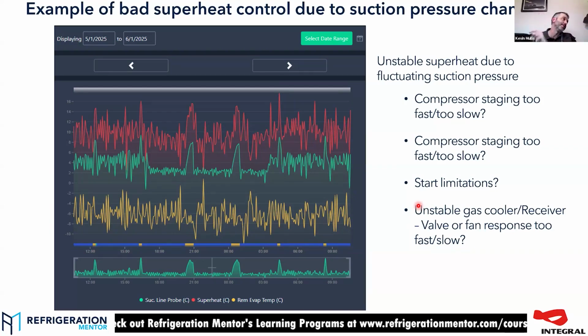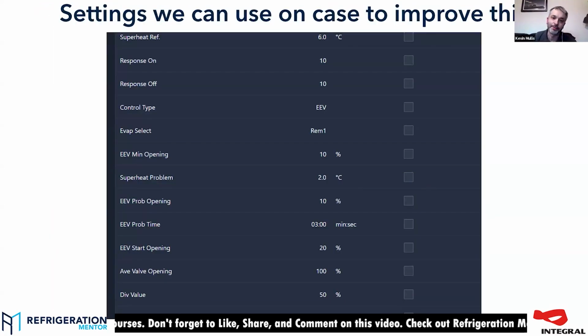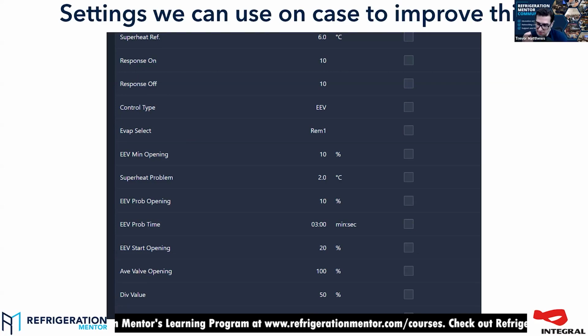Obviously, the other point about keeping the high pressure valve shut to keep the gas cooler pressure up is you start losing pressure in the receiver because it needs to be fed all the time, right? So RDM and some of the other manufacturers give you the option to override what you've told the gas cooler to do if the receiver pressure is getting too low, which is a really useful thing to do. Let's say you're doing heat recovery, you want a high head pressure set point, especially in the winter when you actually want the heat, but you also need the receiver to keep working. So you can tell it, okay, I want 70 bar, 80 bar, but as long as you tell your receiver settings what to do in the event of a low pressure, it'll keep dumping a bit of gas in to feed it. Yeah. Right.